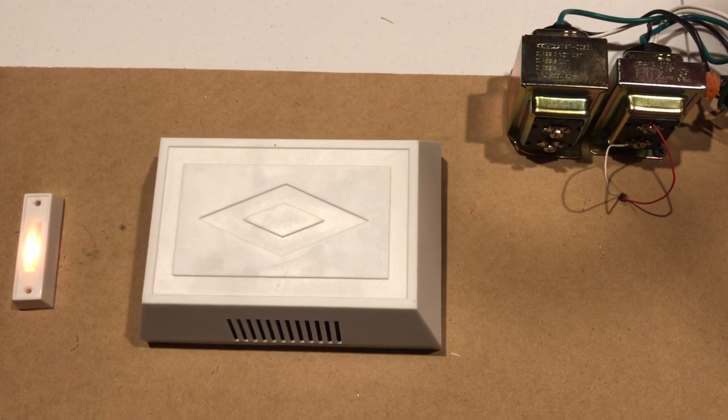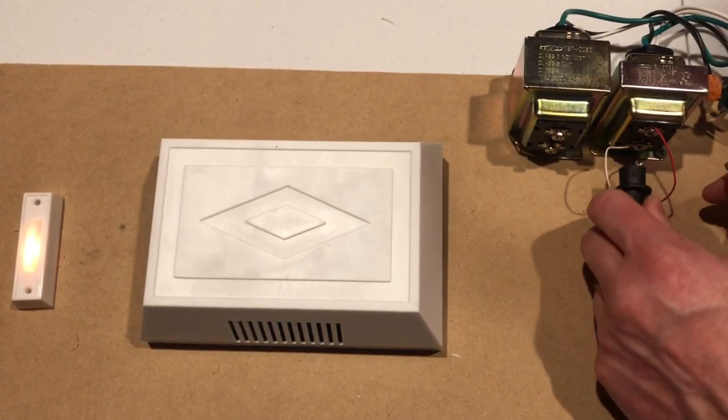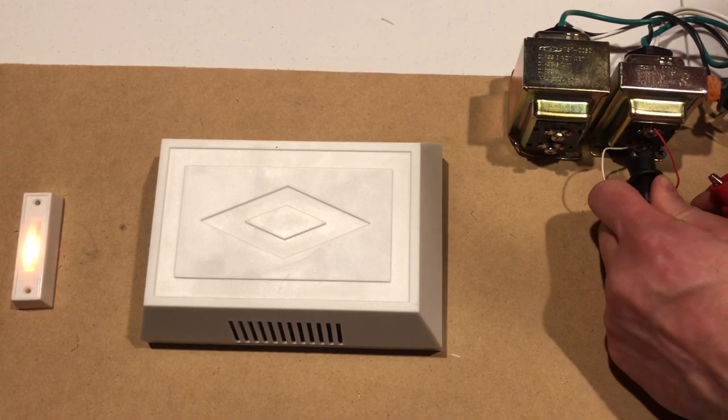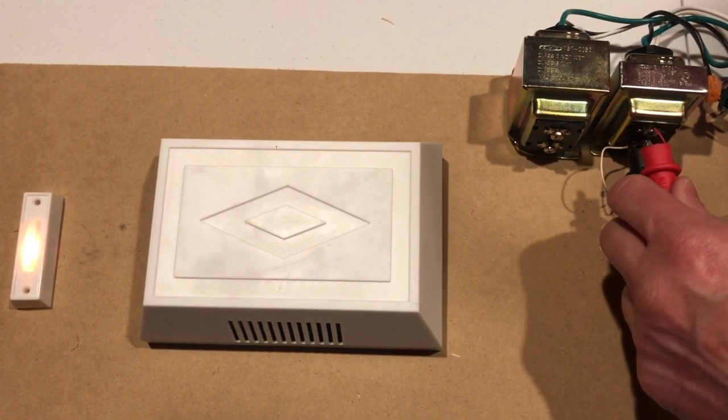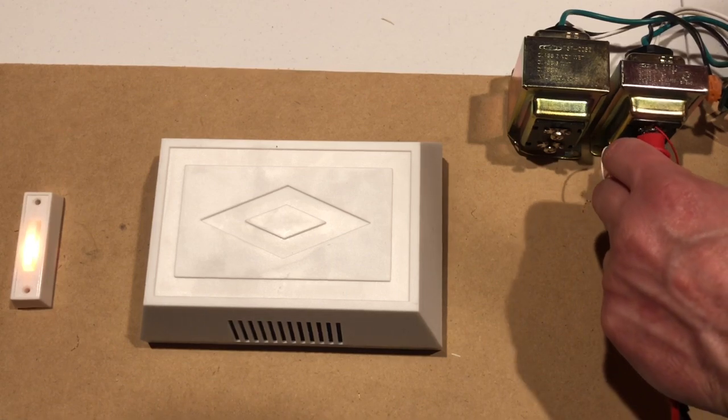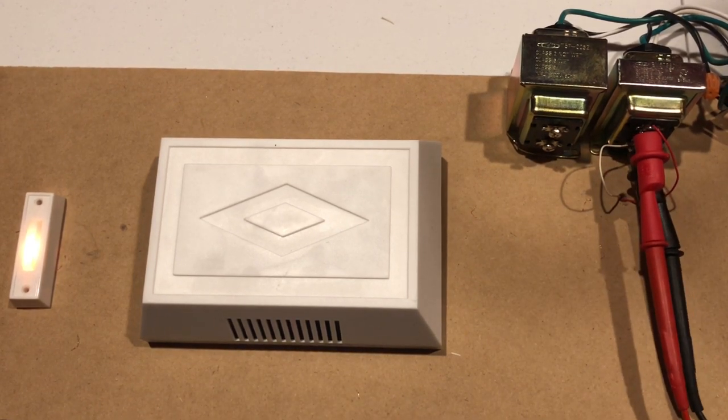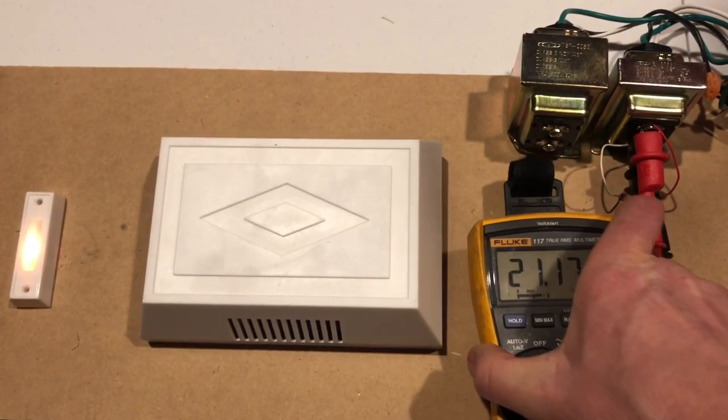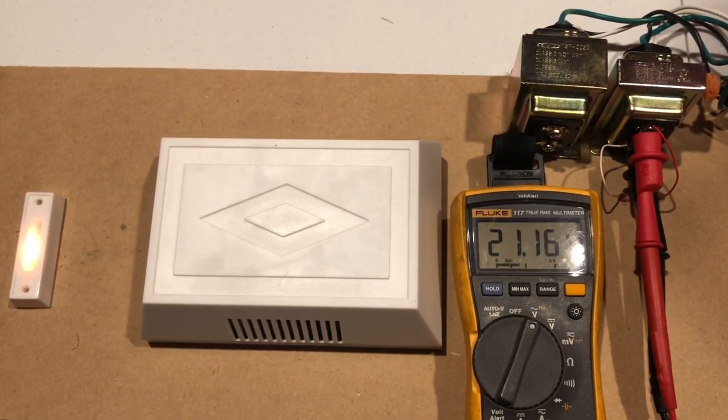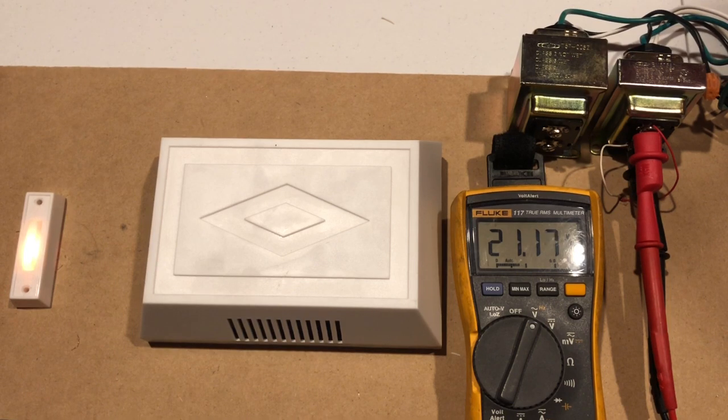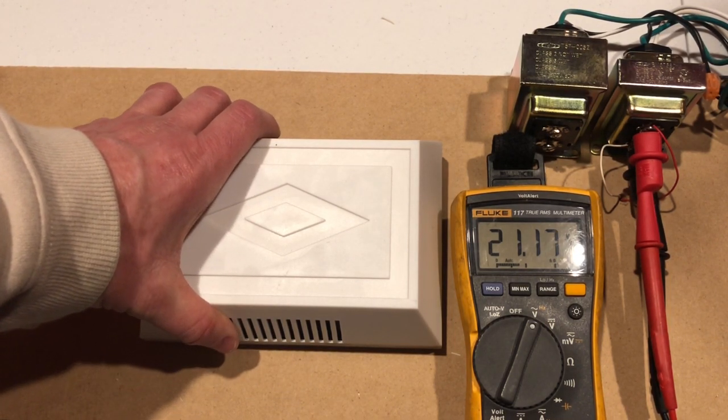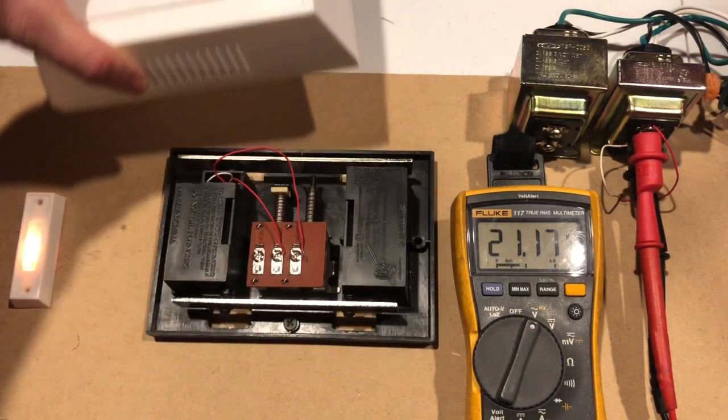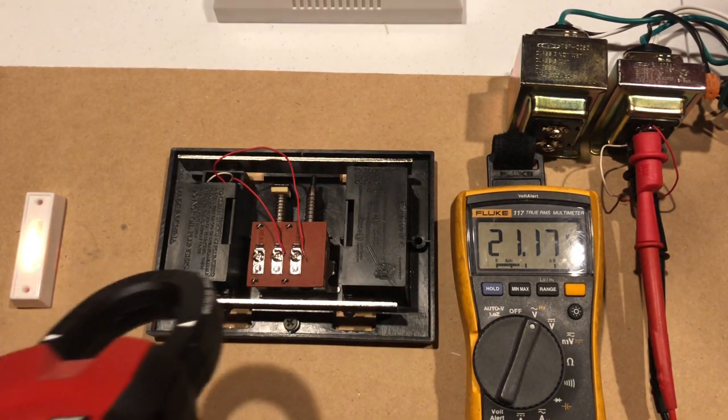First thing I'm going to do is hook up my test leads. We're going to do the 10 VA transformer first and as you can see this one is actually pushing out 20-21 volts. It's supposed to be a 16 volt transformer but it's pushing out 21 volts.